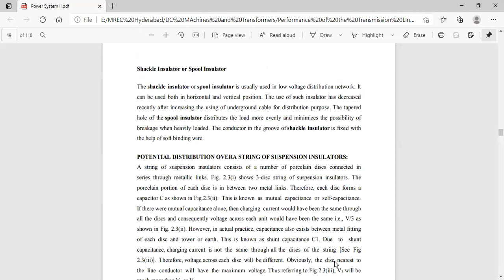Next is the string efficiency. The string efficiency is calculated as the ratio of the voltage across the string divided by N times the voltage across the disc nearest to the conductor. This is the formula we use to find the string efficiency, where N is the number of discs in the string. String efficiency is an important consideration since it decides the potential distribution along the string.